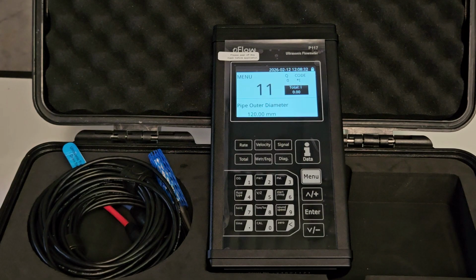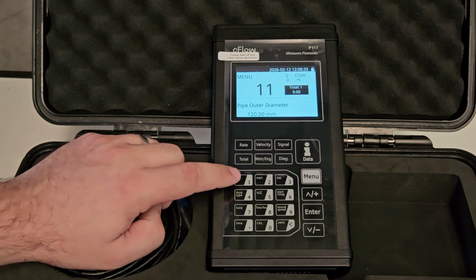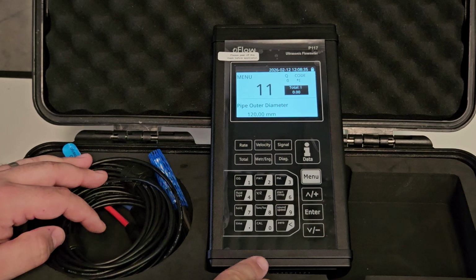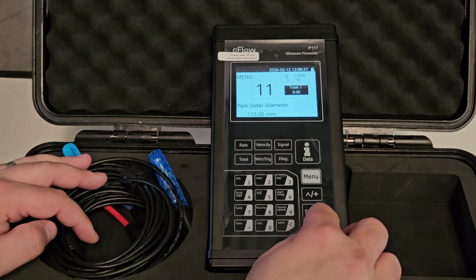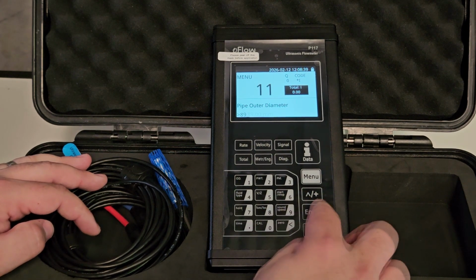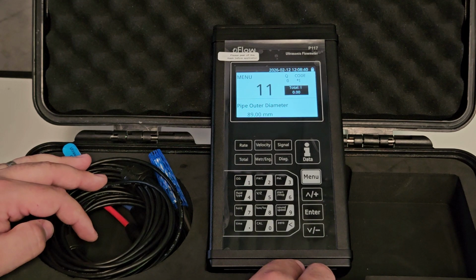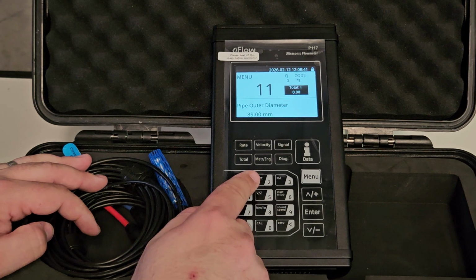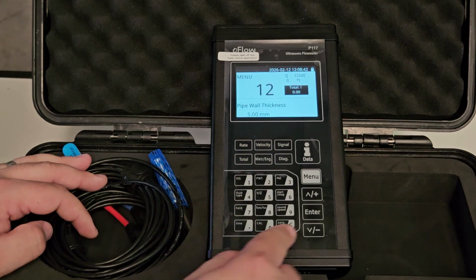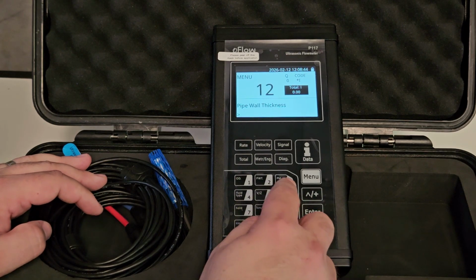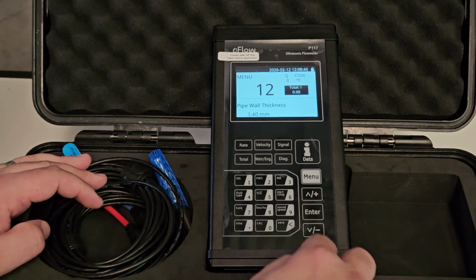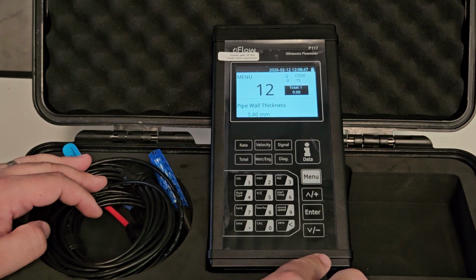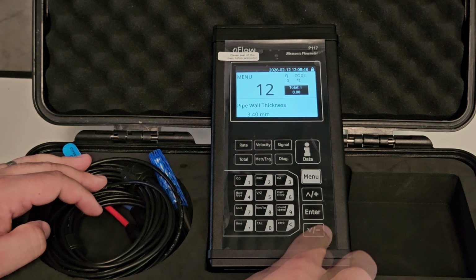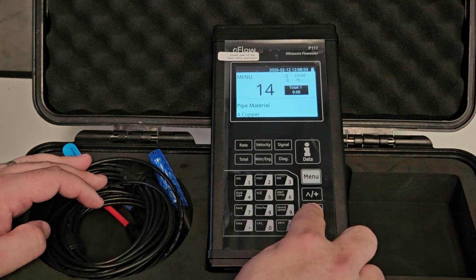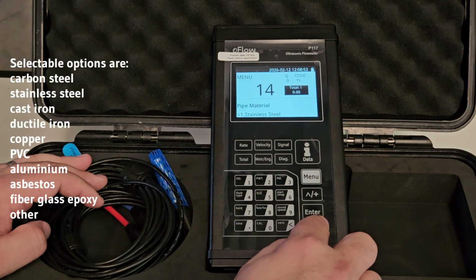The first required parameter is pipe outer diameter. Press the OD shortcut or go to menu 11. Press enter to modify, type the OD, then enter to confirm. Next parameter is pipe wall thickness. Press the shortcut key or go to menu 12. Press enter, type the thickness, and enter to confirm. Next is pipe material. Press the PM shortcut or go to menu 14. Press enter, then up or down to scroll the list of materials and enter to select.